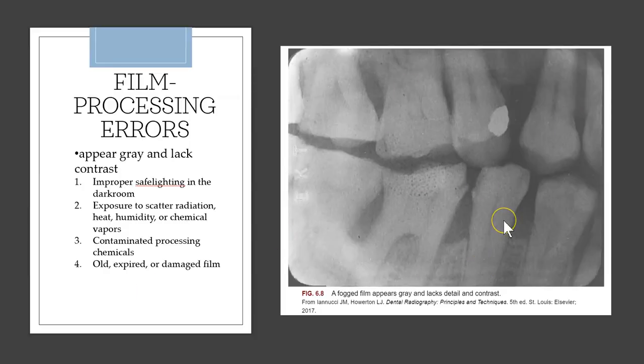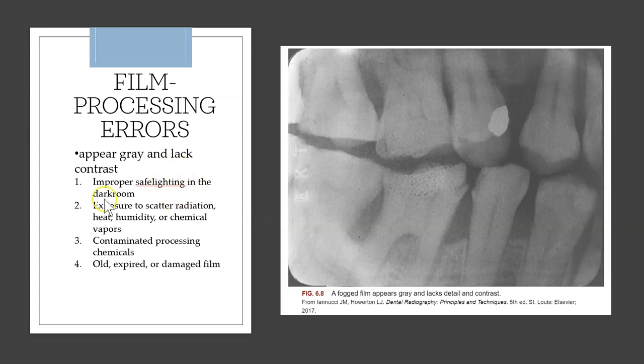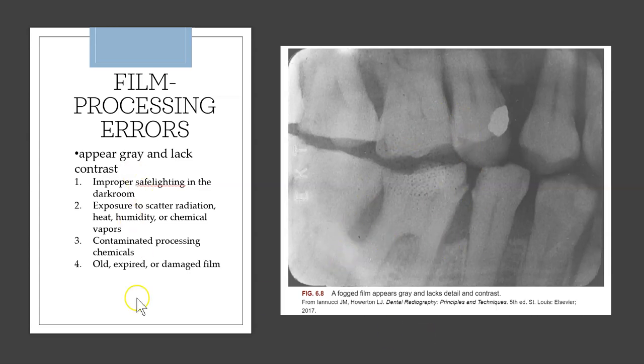Looking at some radiograph images: a gray image lacking contrast is a fogged film. This can happen due to incorrect darkroom lighting, scatter radiation, heat, humidity, contaminated chemicals, or an old film.